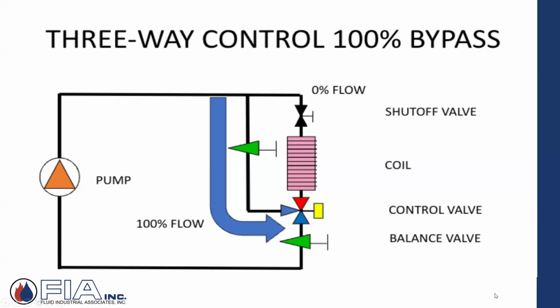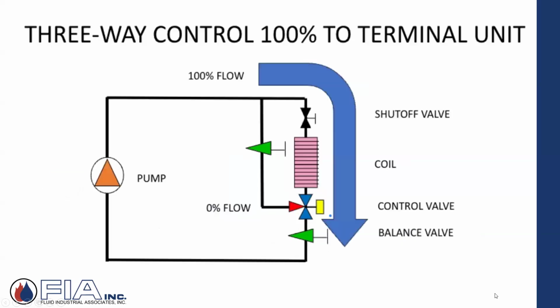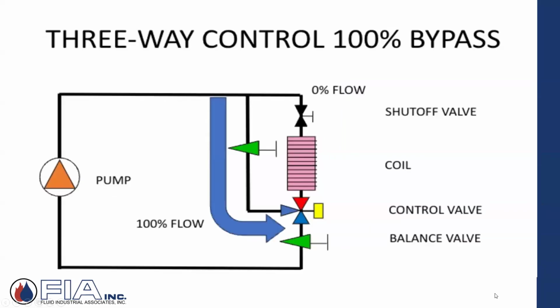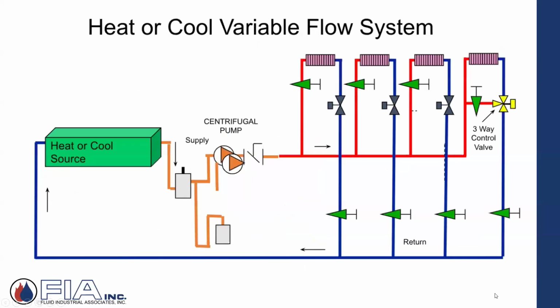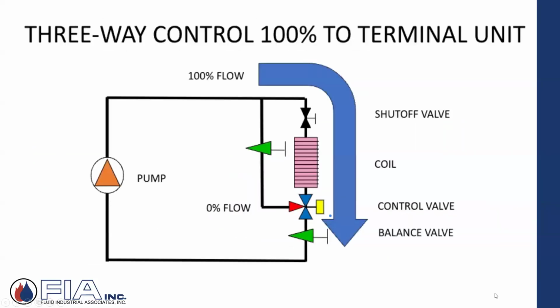So you might call it a bypass valve or a diverting valve. The term almost doesn't matter, it's semantics. But the point was, I'm taking flow and I'm either putting it through the coil or through the bypass, or a lot of times somewhere in between. If I'm throttling, 50% through the bypass, 50% through the coil, even then that changes the pressure drop. So all of a sudden, the pump can still start to slide out on its curve because the resistance changes. If you're putting all the flow through the coil, there's a certain pressure drop. Putting all the flow through that balance valve, there's a pressure drop.